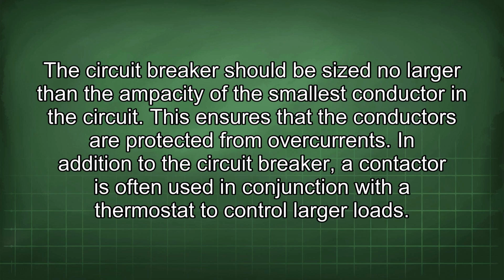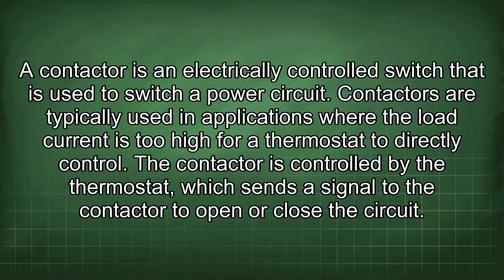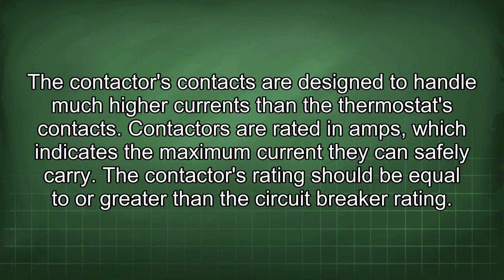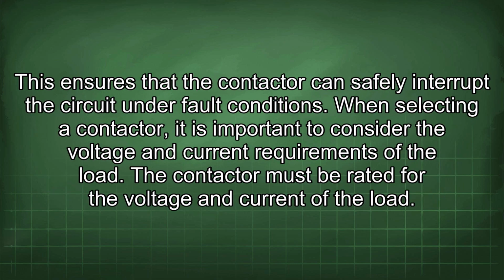In addition to the circuit breaker, a contactor is often used in conjunction with a thermostat to control larger loads. A contactor is an electrically controlled switch that is used to switch a power circuit. Contactors are typically used in applications where the load current is too high for a thermostat to directly control. The contactor is controlled by the thermostat, which sends a signal to the contactor to open or close the circuit. The contactor's contacts are designed to handle much higher currents than the thermostat's contacts. Contactors are rated in amps, which indicates the maximum current they can safely carry. The contactor's rating should be equal to or greater than the circuit breaker rating. This ensures that the contactor can safely interrupt the circuit under fault conditions.